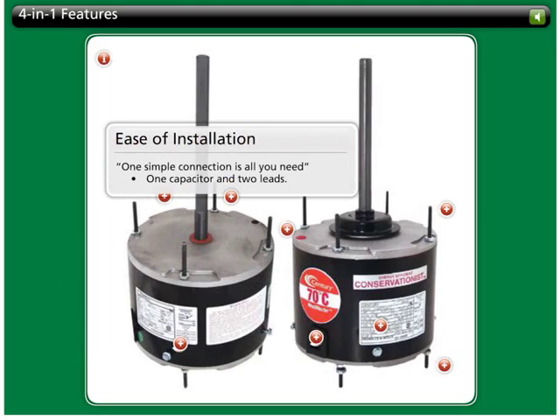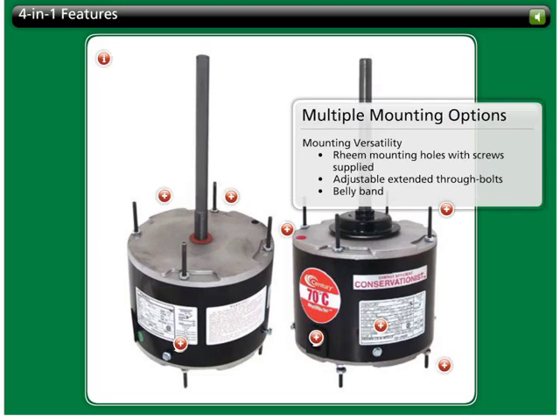Installation is quick and easy because there is only one size capacitor required and two line leads. These motors are versatile enough to be mounted in a variety of ways. 4-in-1 motors will accommodate replacements requiring Rheem mounting, extended through-bolt mounting, and belly band mounting.